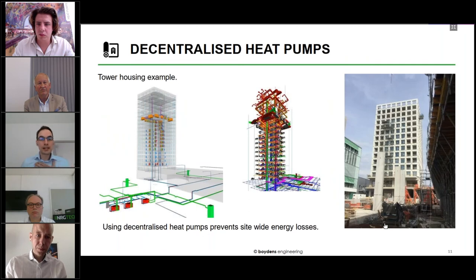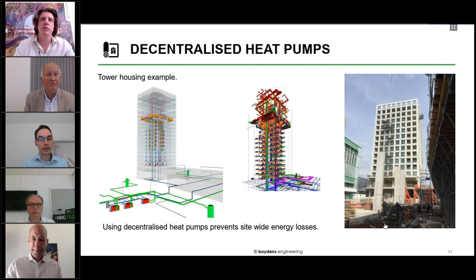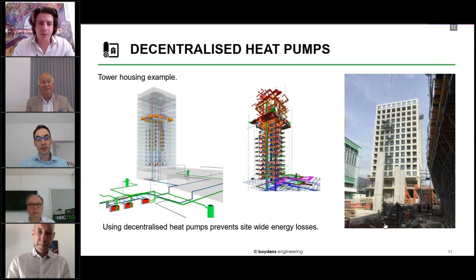Now, about the decentralized heat pumps, there is quite a wide range in powers that are installed, ranging from small heat pumps installed as individual units in apartments, just a few kilowatts, up to several hundred kilowatts of heat pumps that are used for larger buildings in the development, such as a hotel or a shopping center or big air handling units. We can see here on these three pictures examples of those heat pumps, how they are located in the building, and how there is a loop, so the piping that is connecting them.